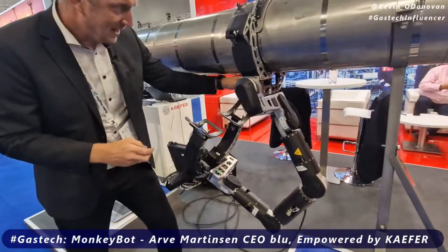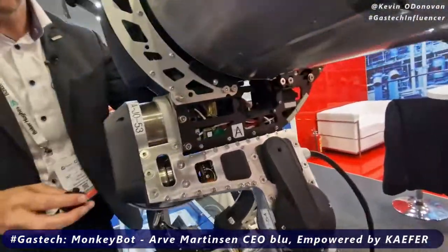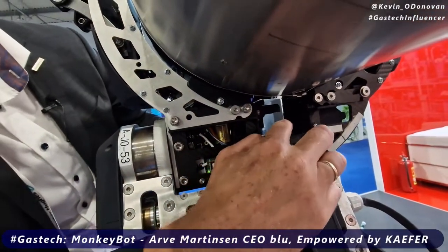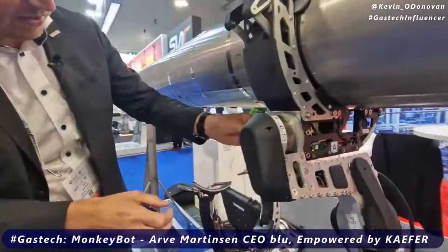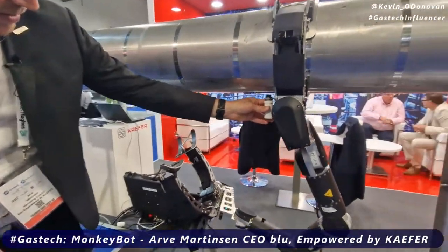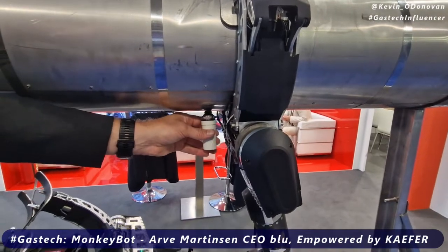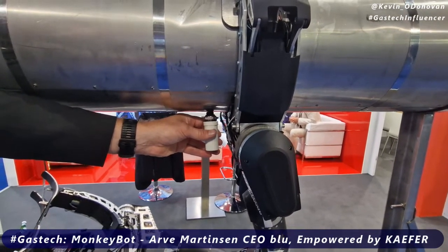We also have the drilling to drill a hole in the steel cladding, and we put a new sensor in as we go. You will install one sensor typically into the steel cladding, just underneath the cladding, so you get to measure the moisture and temperature level.